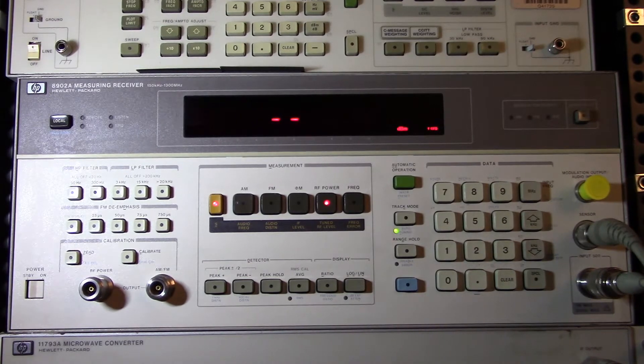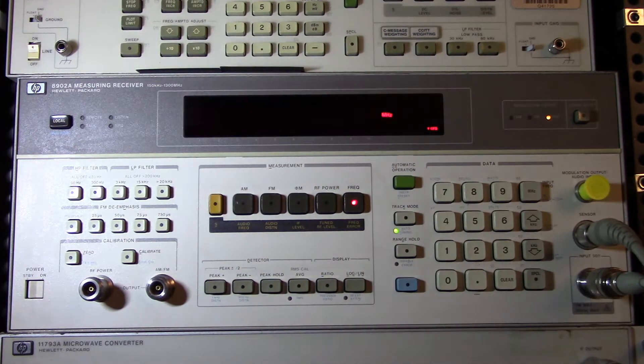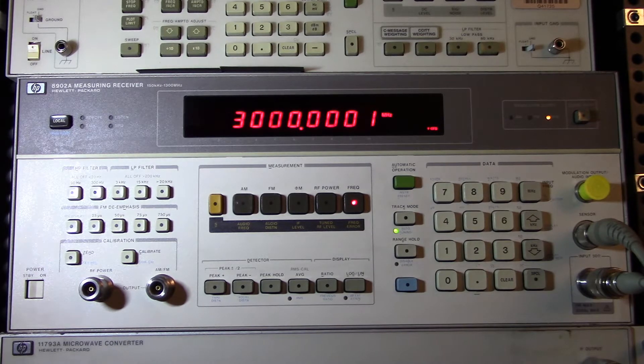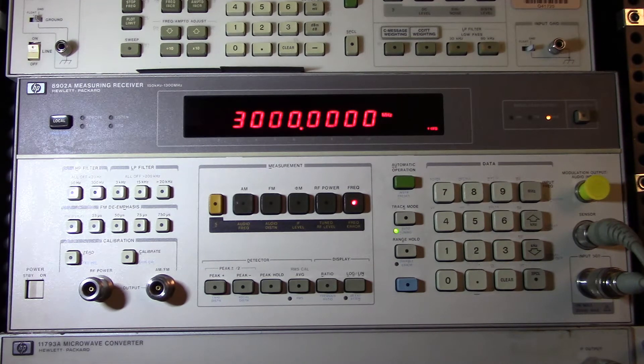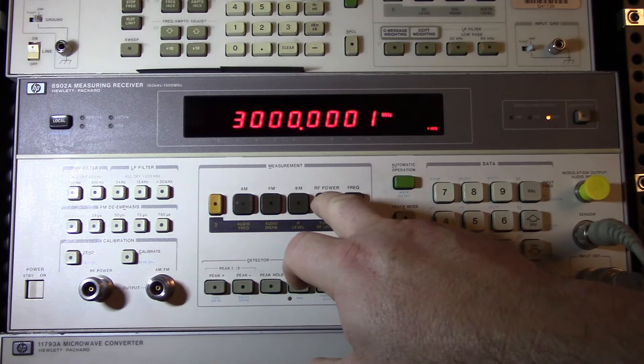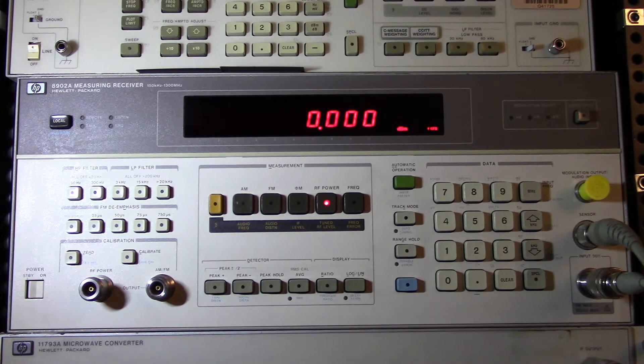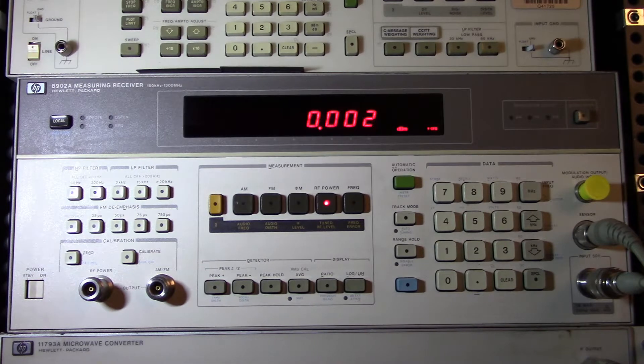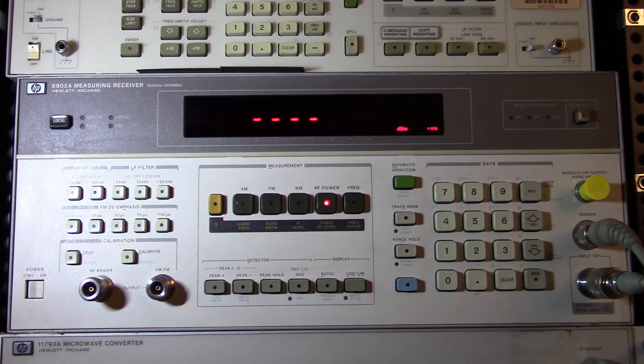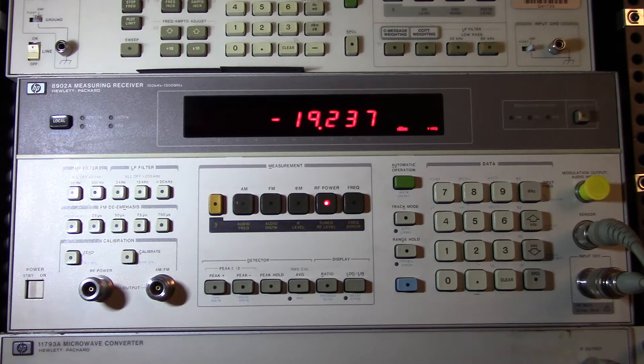By default it goes to three gigahertz, so let's do that and we'll take automatic operation and frequency. Turn the RF on. We're getting a pretty accurate frequency out of that unit at three gigahertz. Let's take a look at the RF power. I had previously run it up on the power thing, so zero dBm, it's pretty bang on accurate there. Let's drop that down a bit. Let's say minus 20 dBm. Yeah, that's not bad. Let's return it to zero dBm.